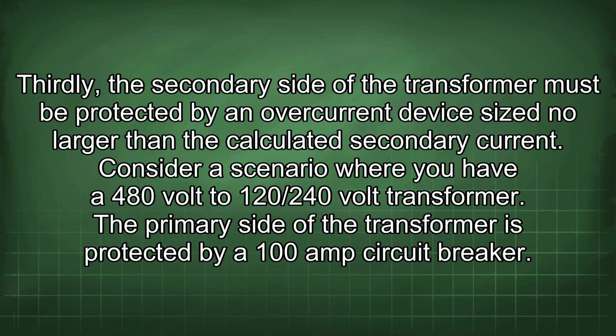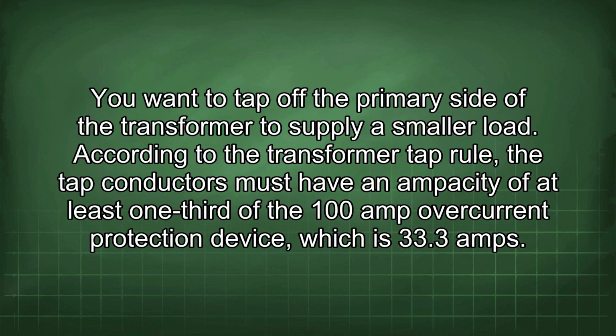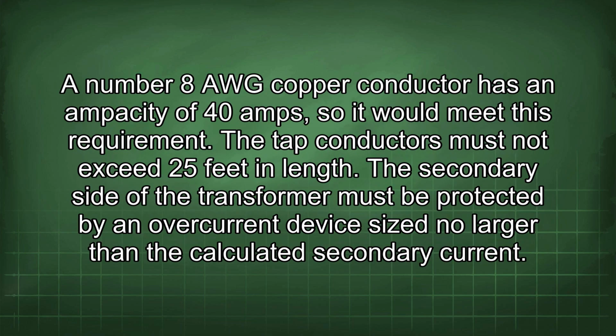Consider a scenario where you have a 480 volt to 120/240 volt transformer. The primary side of the transformer is protected by a 100 amp circuit breaker. You want to tap off the primary side of the transformer to supply a smaller load. According to the transformer tap rule, the tap conductors must have an ampacity of at least 1/3 of the 100 amp overcurrent protection device, which is 33.3 amps.